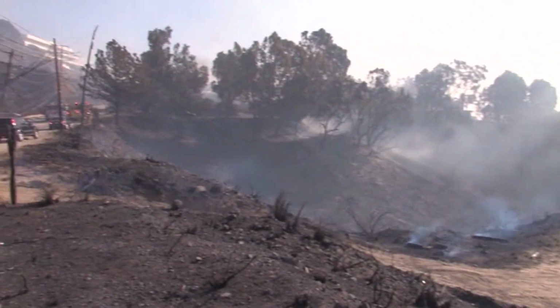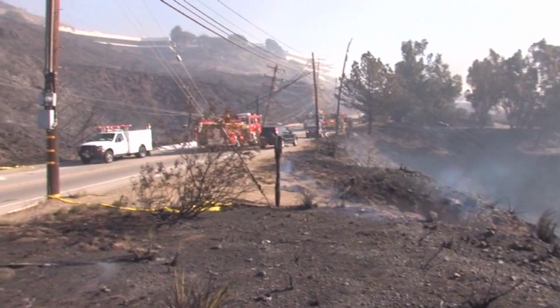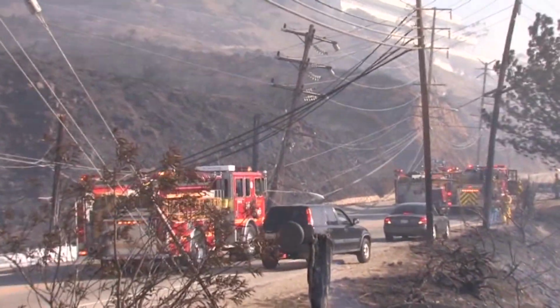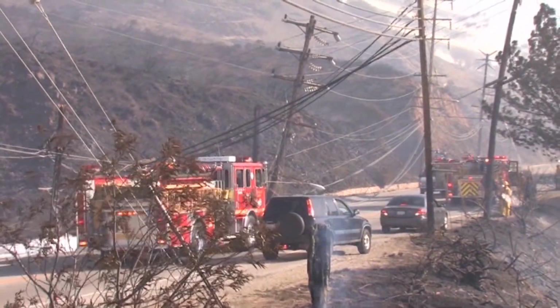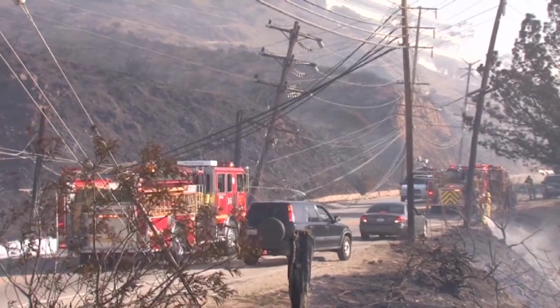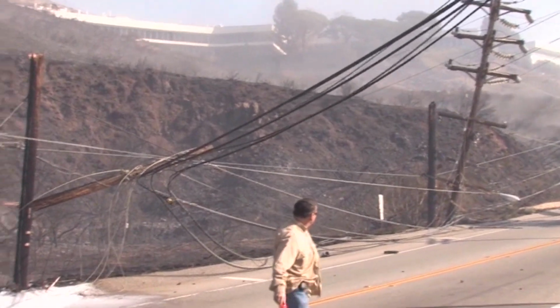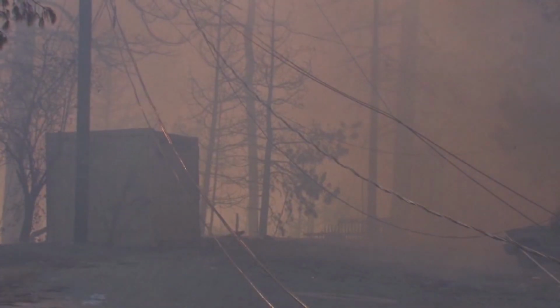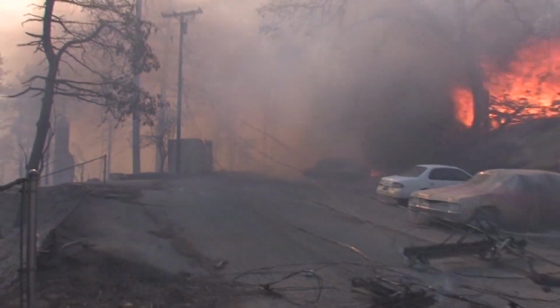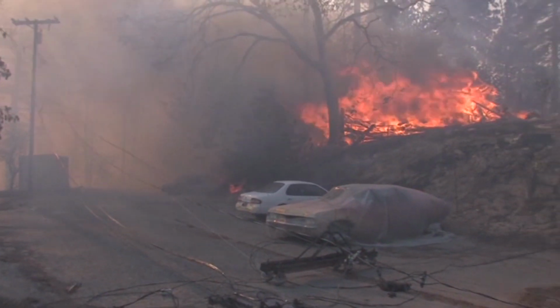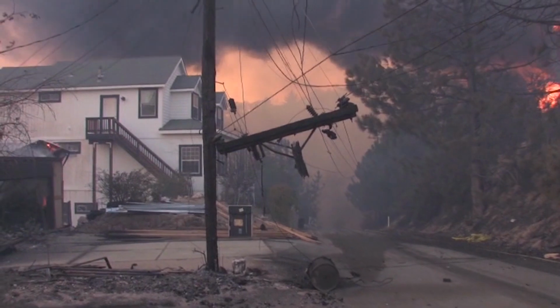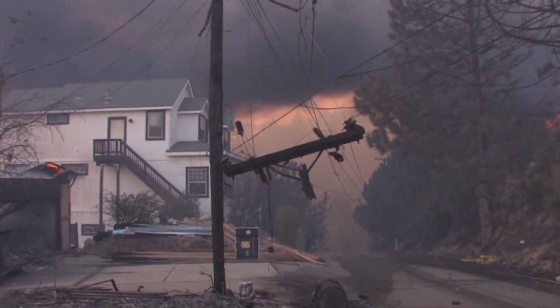Extinguish pole fires below high voltage conductors and equipment in wildland fire areas as soon as they are discovered. Burning or smoldering poles left behind in a burn area may eventually end up as wire down hazards for first responders. These downed wires and poles can also block escape routes without warning. All personnel should take special precautions to avoid downed wires during and after a wildland fire.